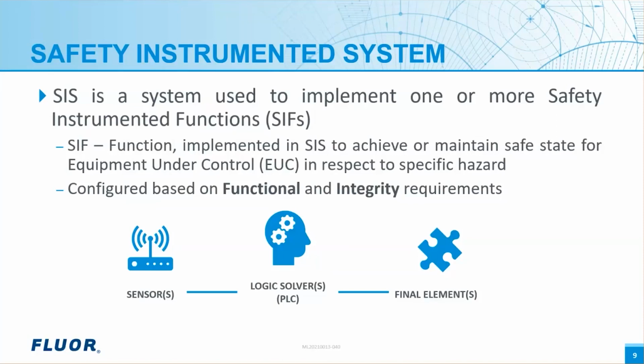So the next attribute that I've mentioned is the integrity requirements, and they are expressed in terms of safety integrity level, or SIL, ranging from SIL 1 to SIL 4. Based on the assessment of risk associated with a scenario, which is typically done in a SIL assignment workshop, the risk reduction required to achieve is determined. This will then provide the integrity requirement for the SIF expressed as SIL.